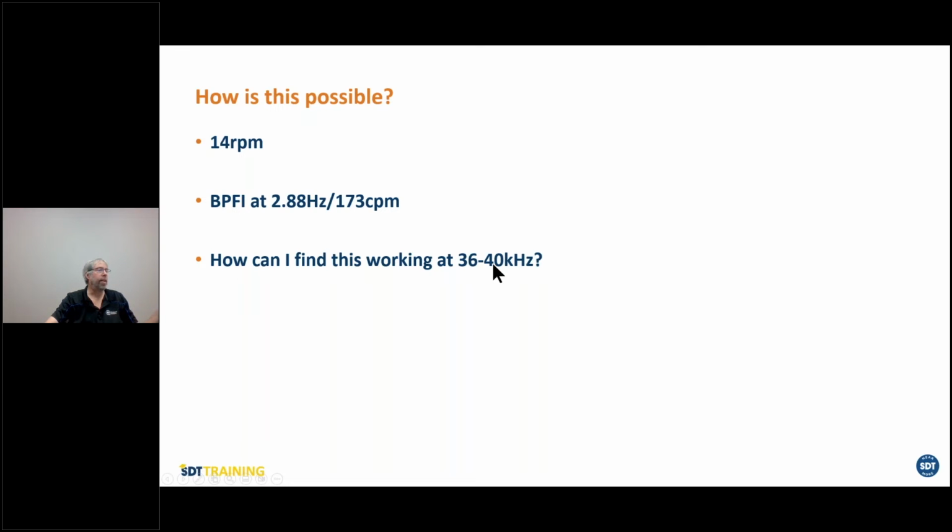Why does it work at 30 to 40 kilohertz? Because, as I mentioned before, using a tuned system, our pickup is tuned with our instrumentation. Anything occurring at high frequency, like impacts, will obviously be amplified. That makes our system a much more powerful one to detect amplitudes at very low frequencies.